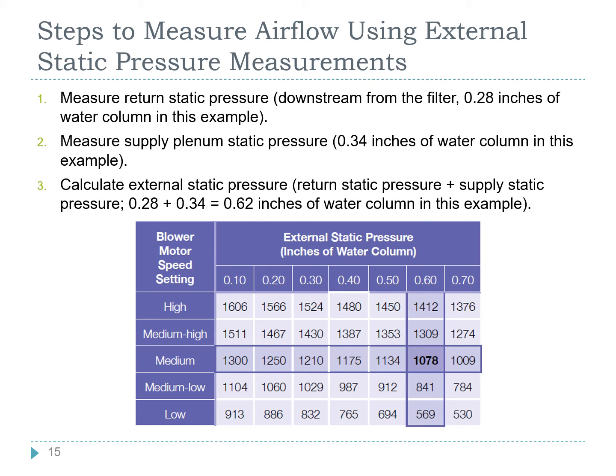Continuing with steps to measure airflow using external static pressure, we've measured the return static on the furnace side of the filter, and we had 0.28 inches of water column in this example. And we've also measured the supply static pressure. We had 0.34 inches of water column also for this example. Then we calculate the static pressure. We take 0.28 plus 0.34, and that equals 0.62 inches of water column for this example.